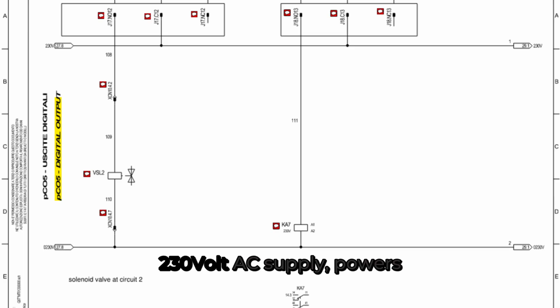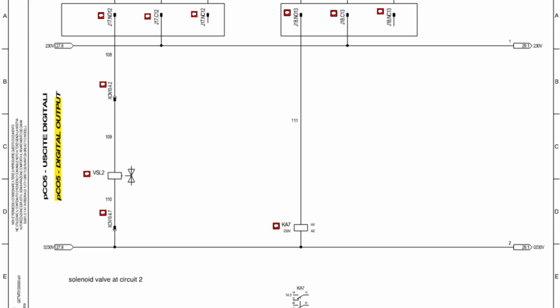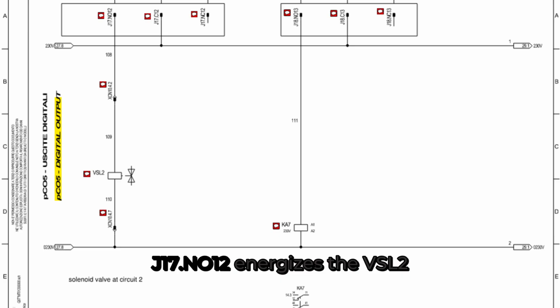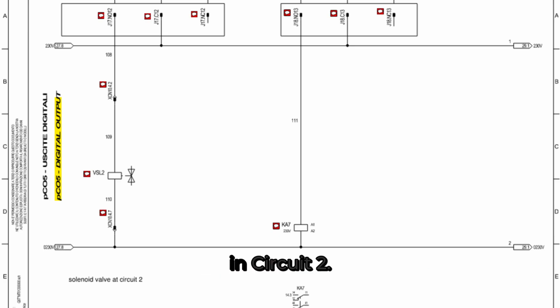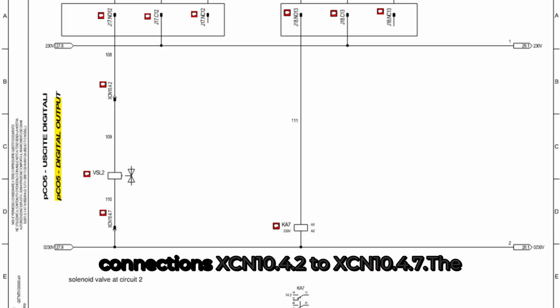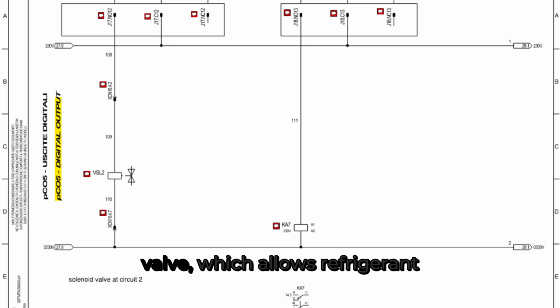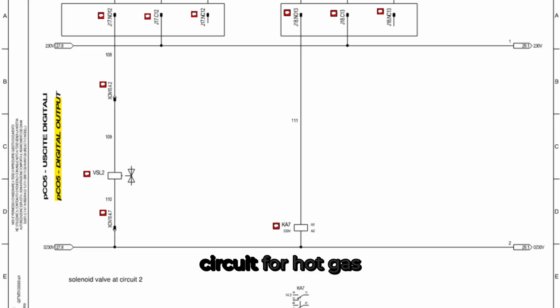At the top, the 230-volt AC supply powers the relay outputs in 2 separate blocks. J17-NO12 energizes the VSL2 solenoid valve relay coil, which controls refrigerant flow in circuit 2. It's wired through terminal connections XCN 10.4.2 to XCN 10.4.7. The coil energizes, opening the valve, which allows refrigerant to flow through the circuit for hot gas injection. On the right side, at J18-NO13, we see KA7, a 230-volt relay coil, an optional base heater for the heat pump.